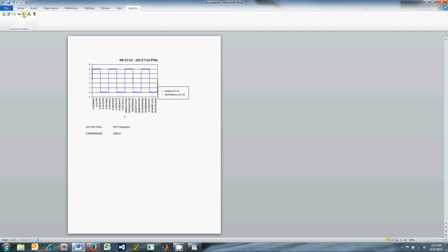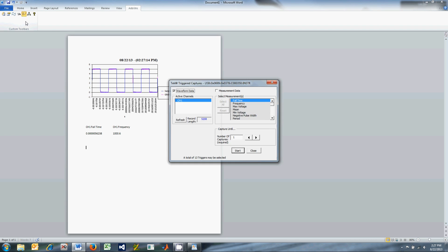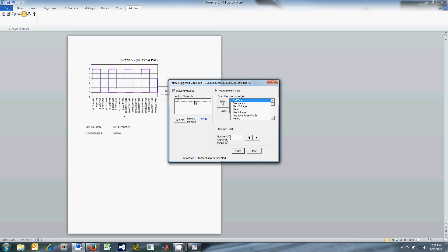The next button is TekW Triggered Captures, which is a combination of TekW Waveforms and TekW Measurements and can be used to save waveform data and capture measurements simultaneously. Select the box next to the functions you want to use, select the desired channel and measurements, and the number of captures that you desire, and then select Start.